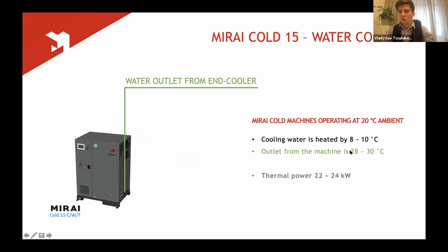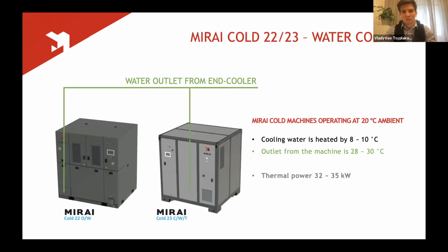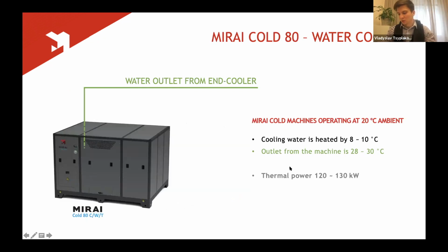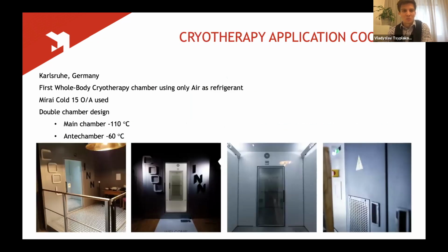So this is the heat that you can go and put into a heat pump to heat it further. And coming down with bigger machines, we can get 35 kilowatts. And with the biggest machine, which we are going to announce later this year, we can harvest about up to 130 kilowatts of thermal power, but once again, with a low temperature, not higher than 30 degrees. You can cool the machine with 30-degree water, then you would have a 40-degree water outlet, but still it's a low potential heating.